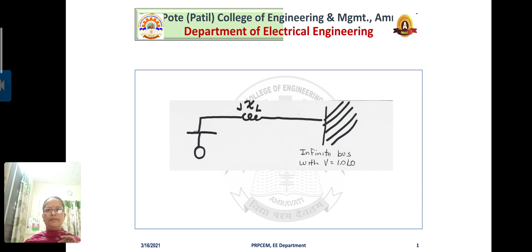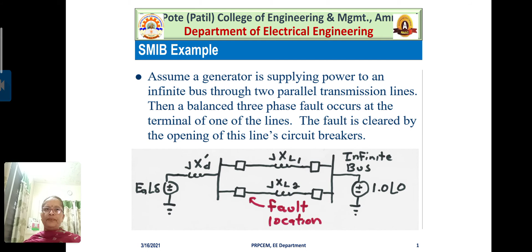So consider that example again. Assume a generator is supplying power to an infinite bus through two parallel transmission lines. You can observe this diagram carefully. Then a balanced three-phase fault occurs at the terminal of one of the lines. You can see the fault location here. The fault is cleared by the opening of the line circuit breakers. Now let us see what happens in the system for such a condition.